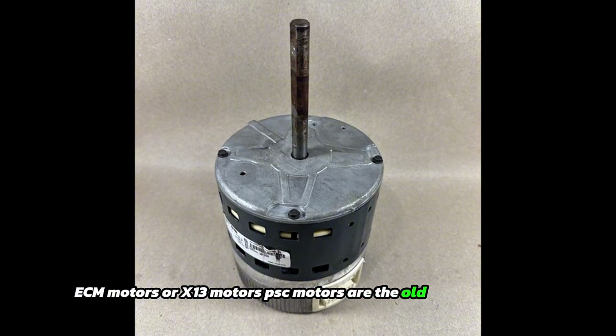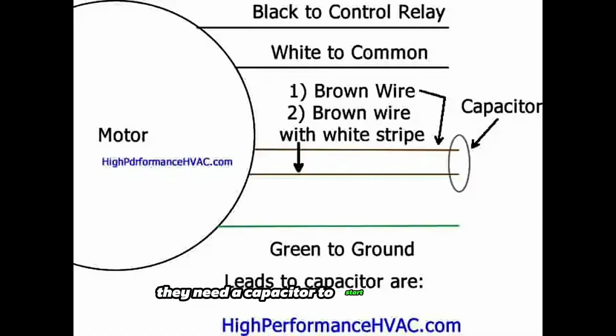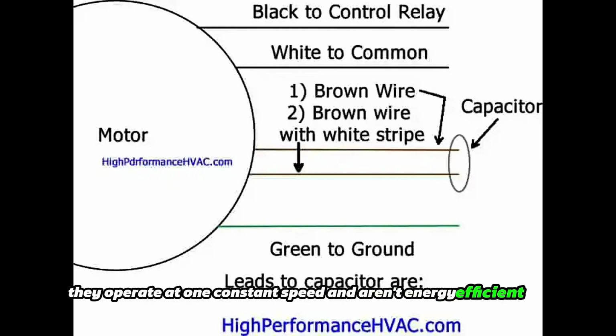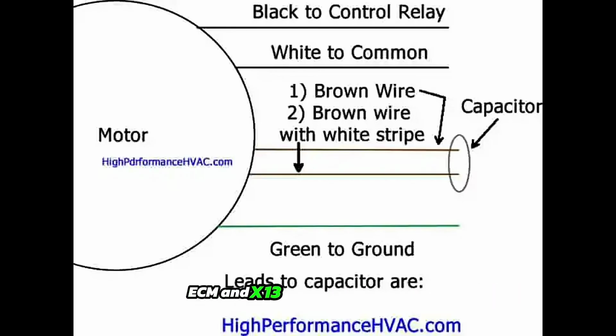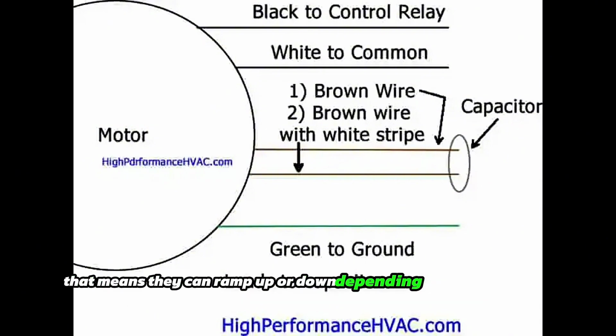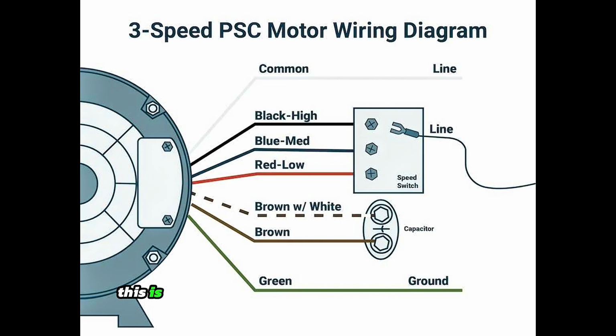PSC motors are the old-school type. They need a capacitor to start and run. They operate at one constant speed and aren't energy efficient. ECM and X13 motors, however, are electronically controlled and variable speed. That means they can ramp up or down depending on the system demand. This is a big deal for comfort and energy savings.